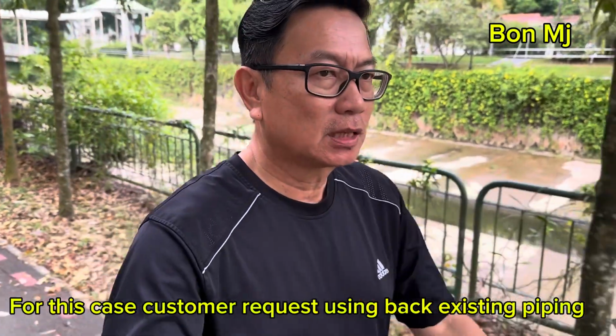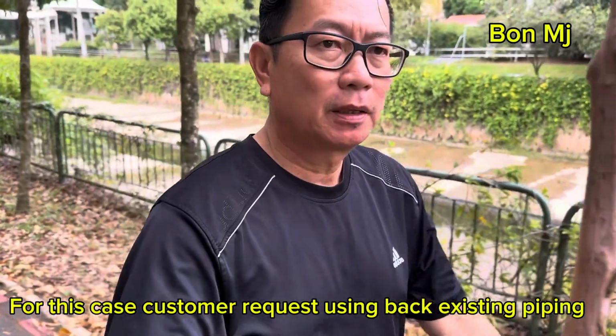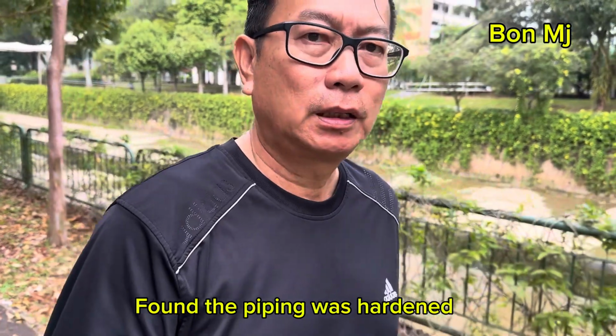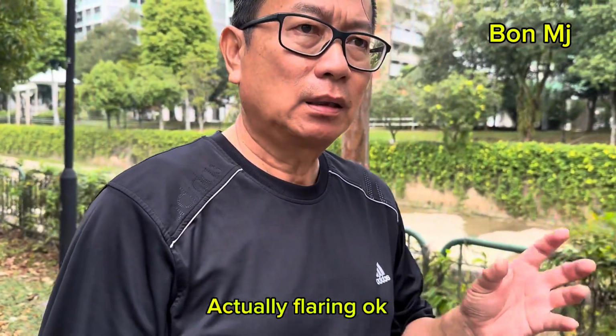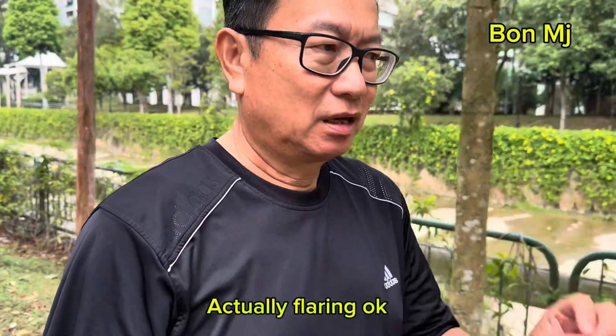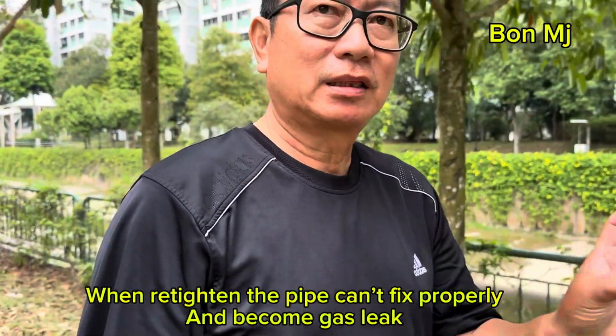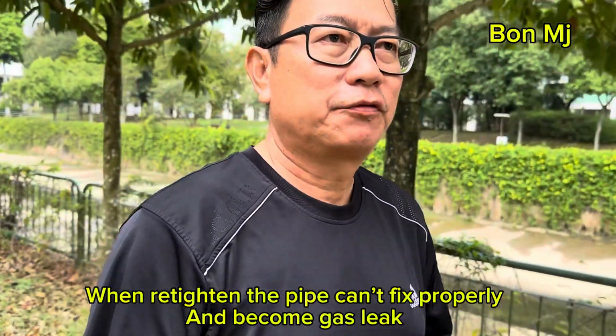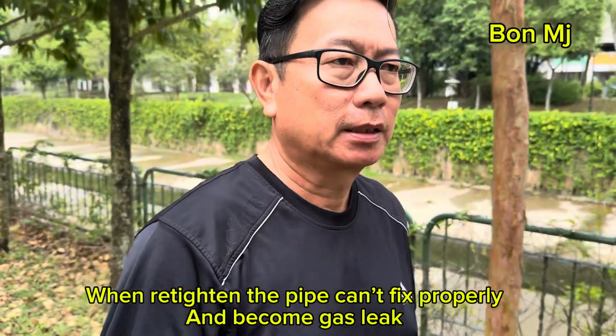For this case, the customer requested using back the existing piping. Okay, I found the piping is hardened. And the flaring, actually the flaring is okay, but the pipe is hardened. When you retighten, the pipe cannot fix properly and it becomes a gas leak.